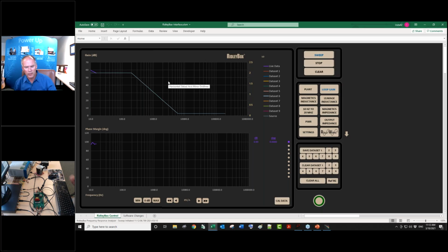Many of you will have noticed, by the way, our analyzer talks to you, and it becomes kind of addicting, actually. I get a little disconcerted if I don't hear the analyzer working anymore. So that was a nice touch our programmer put in for us to have it speak. So here we're sweeping from 10 Hertz, 20, 30.